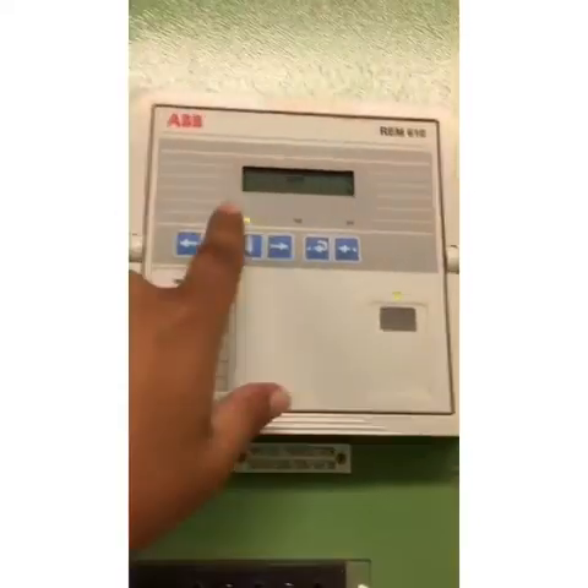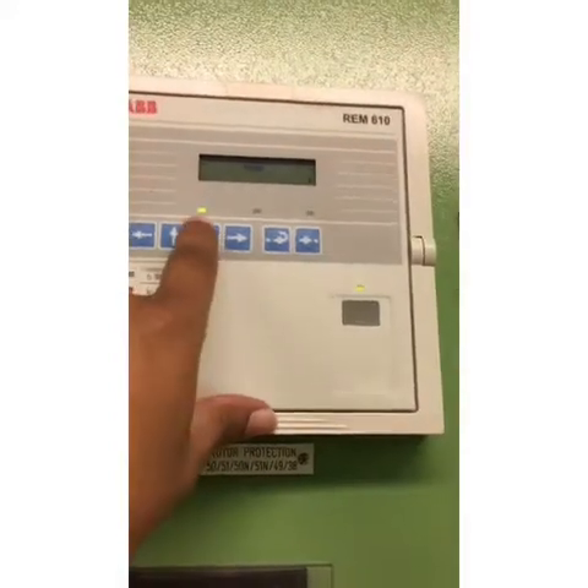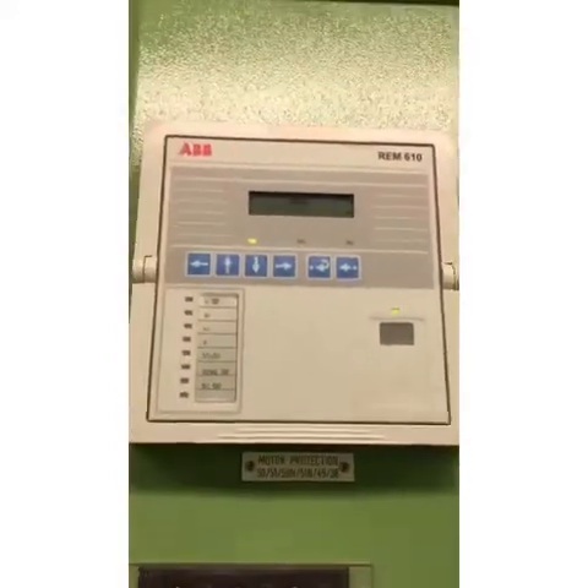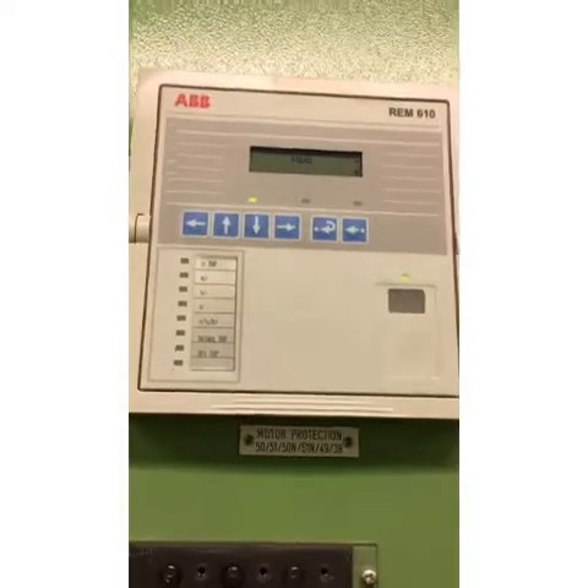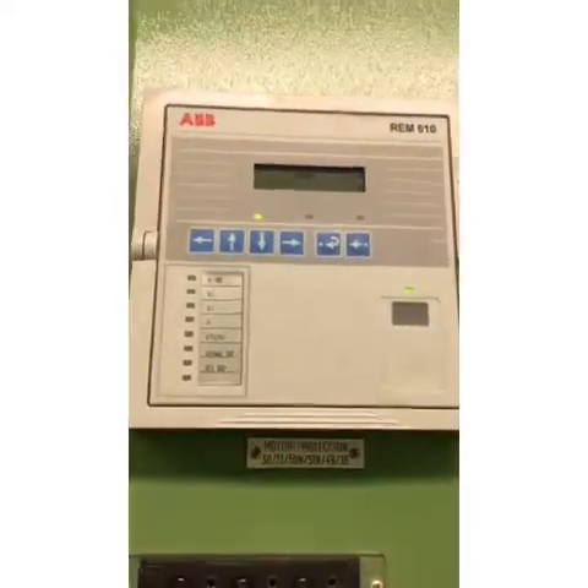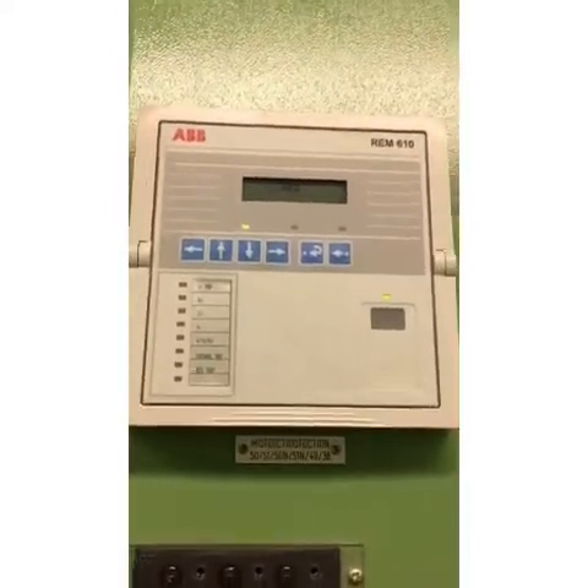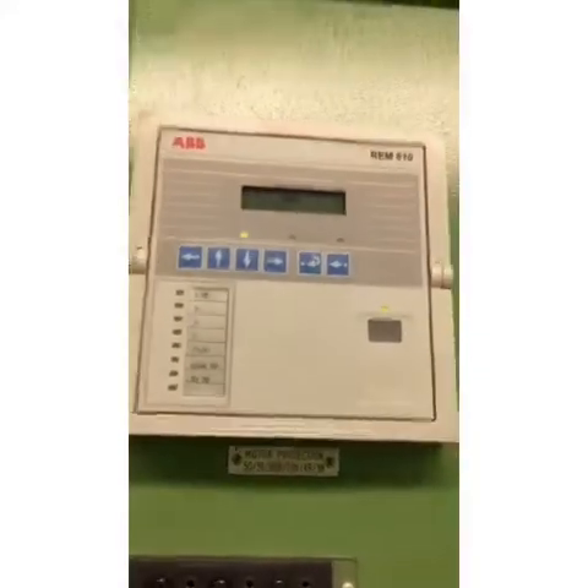We have 3 LEDs here. This one means the relay is available. If this one was blinking, it means there is something wrong, and the message will come here, internal fault. I will give a fault signal now, and we will see how to reset it.